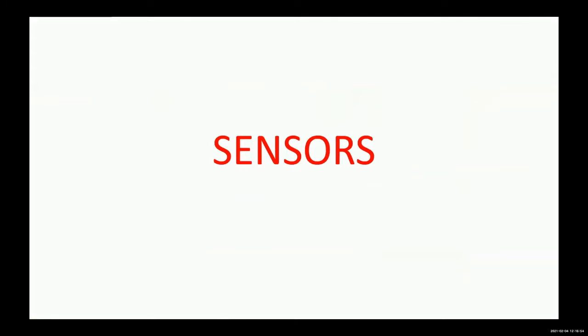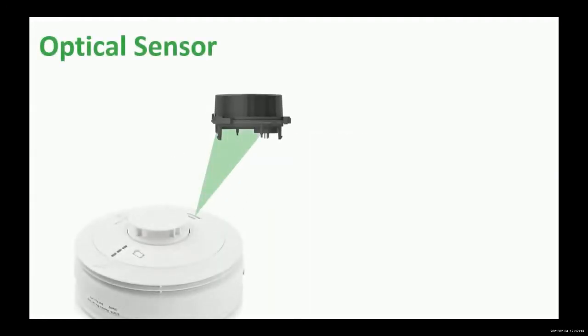Okay, so we'll move on to the different sensor types in relation to the installations themselves. And once we get the information on the sensors out, it will equate to the graphic you saw earlier in relation to the design installation from the IS 3218 standard. So we'll first of all have a look at the optical sensors. The optical sensor, I suppose, historically has been the less used of the smoke detectors for the simple reason it's a bit more expensive to manufacture than the ionization type, but it's probably the more stable type to be used in residential premises. And again, we'll see this from the color and the graphics later on in relation to the location of these devices. It's more than likely the device of choice within the premises at this stage.